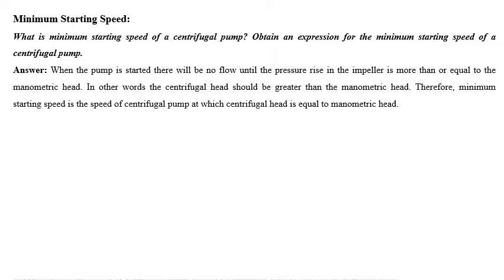When the pump is started, there will be no flow until the pressure rise in the impeller is more than or equal to the manometric head. In other words, the centrifugal head should be greater than the manometric head. Therefore, the minimum starting speed is the speed of the centrifugal pump at which the centrifugal head equals the manometric head.